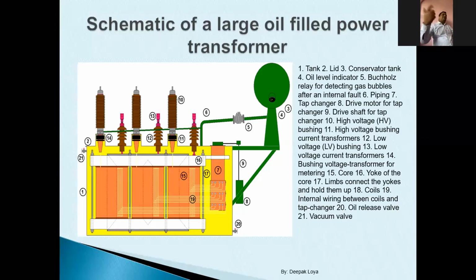Now I can have external CTs, where the CT is mounted outside the transformer as separate equipment, or I can have them mounted on the top of my transformer tank, below my bushings. Those are ring type CTs, and often they are termed bushing CTs. The portion of the tank in which those are housed is called a turret. So my conductor will be passing through that ring type CT. That will be the primary of my CT, and the turns wound in the form of a ring will be the secondary side of my CT. Those CTs may have a rating like 1600 by 1 or 5000 by 1.